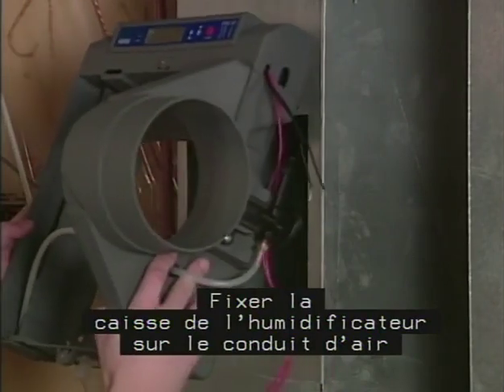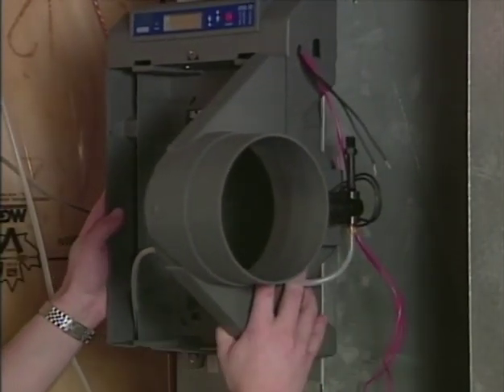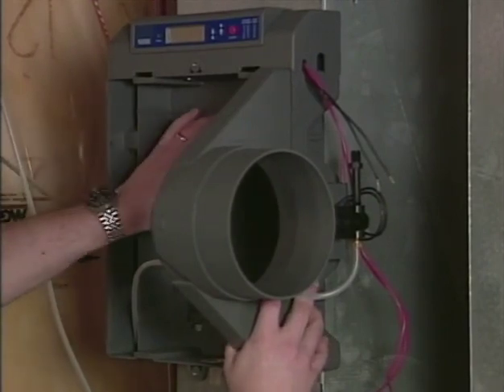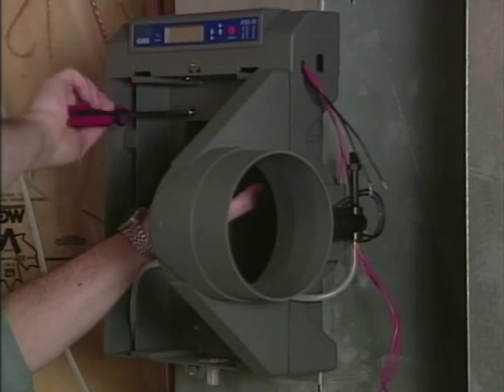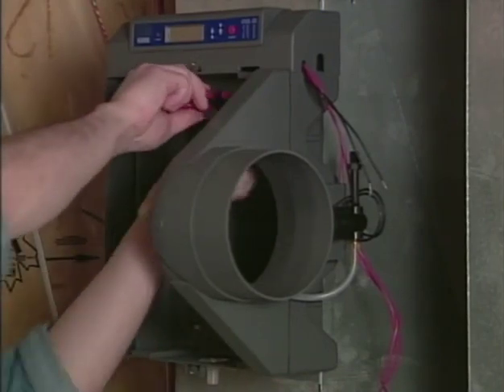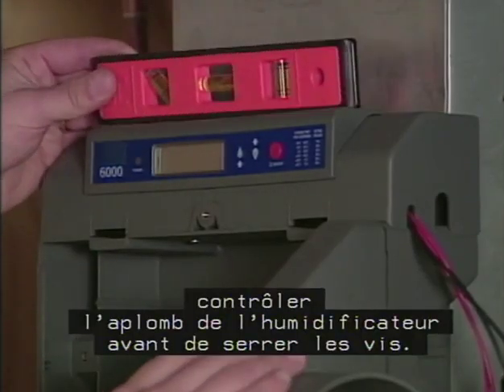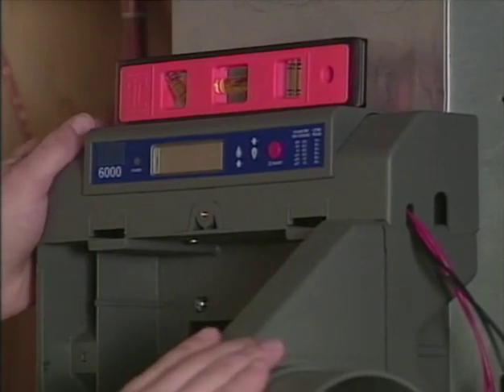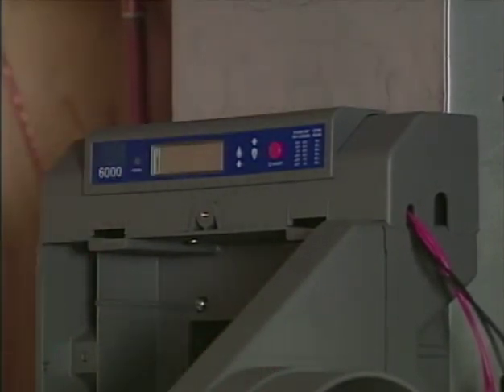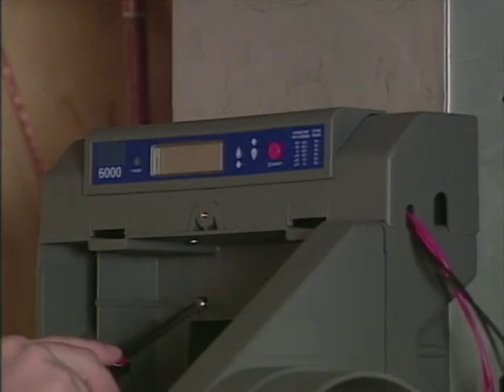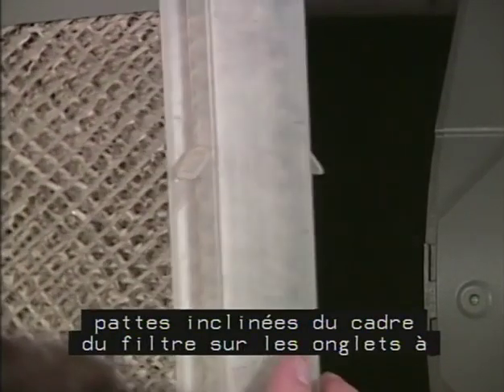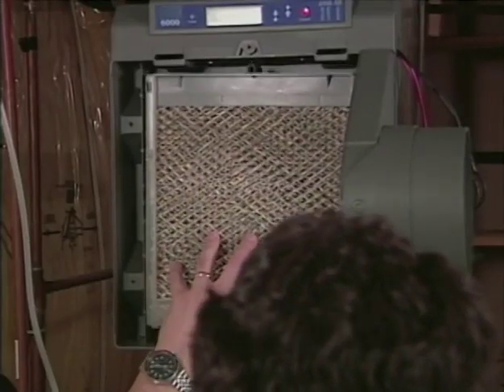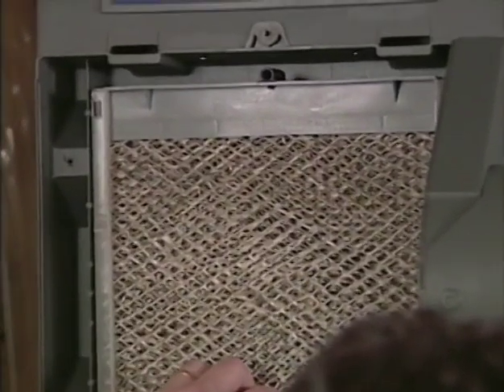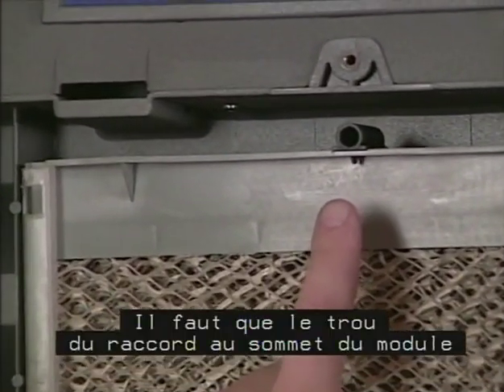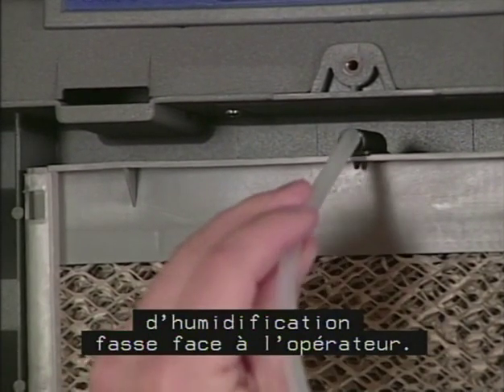Mount the humidifier cabinet on the duct with 4 of the screws from the installation package. Level the humidifier before tightening the screws. Replace the evaporator pad assembly by hooking the slanted tabs on the filter frame onto the tabs on the back of the humidifier cabinet. Make sure the hole in the nozzle on the top of the evaporator pad assembly is facing you. Firmly insert the water tube into the nozzle.